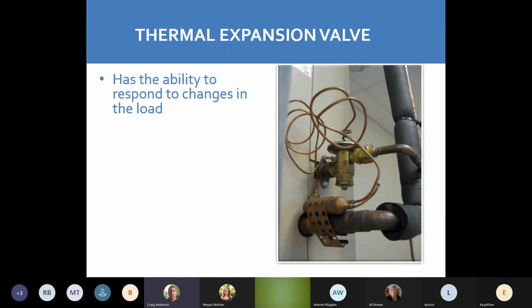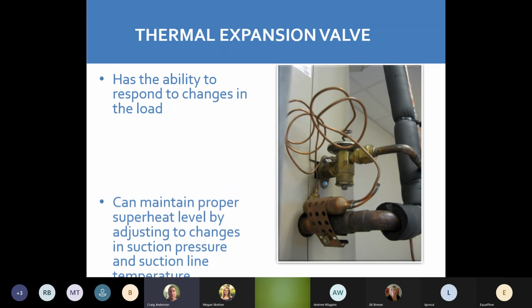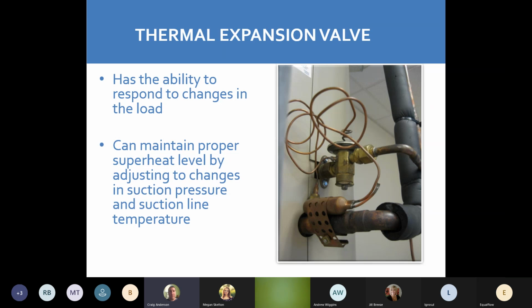So the TX valve has the ability to respond to change in the load, and can maintain a proper superheat level by adjusting to the changes in the suction pressure and the suction line temperature. So if you notice in the picture, we have our TX valve and then we have a probe that's on our suction line. So it is monitoring the temperature of that suction line and telling the TX to open or close. Where a standard piston is, this is what you're getting all the time, doesn't matter. Where our TX is going to actually try to monitor and keep that flow steady.